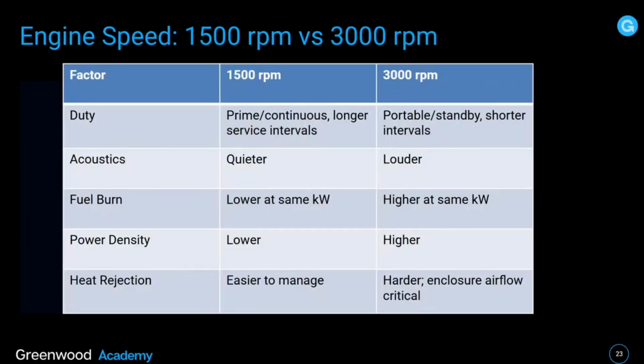Now let's look at the engine speed. You've got 1500 RPM versus 3000 RPM, and you can see with this particular table, heat rejection, for example, is easier to manage with a 1500 RPM unit than, say, a 3000. Obviously, on acoustics, 3000 RPM is definitely louder, considerably louder. Now, the loudness of gensets is measured in decibels, and this is a logarithmic scale. So the difference between, say, 55 dB and 65 dB is considerable, and you must take that into consideration as part of your selection criteria.